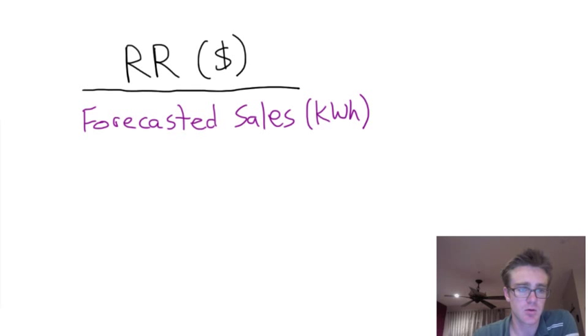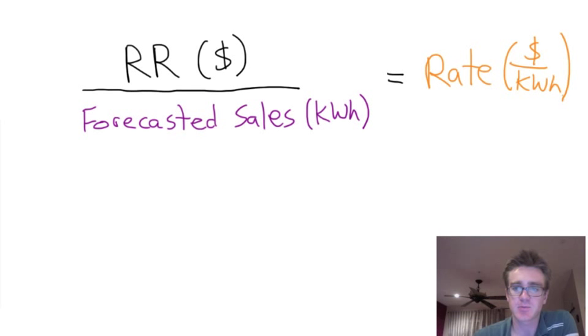So, we just divide this through and revenue requirement divided by forecasted sales equals the rate, which is going to be in dollars per kilowatt hour. So, through the rate case process, this rate is set.